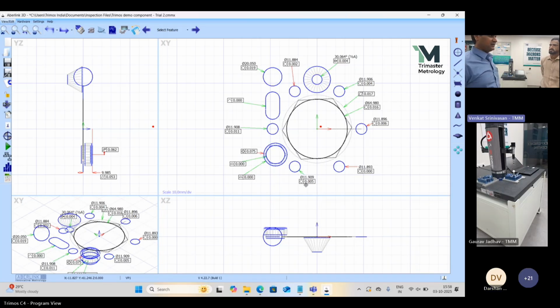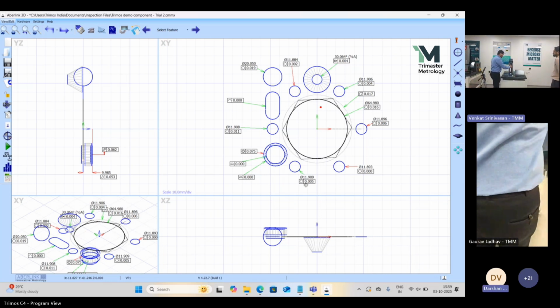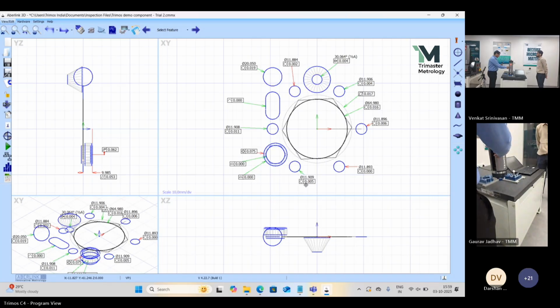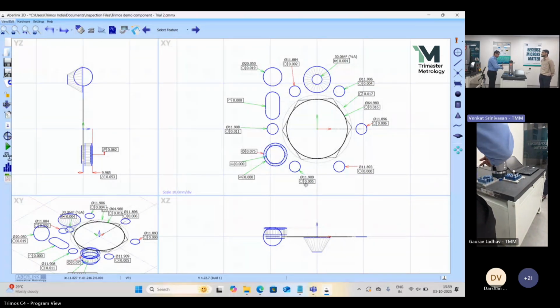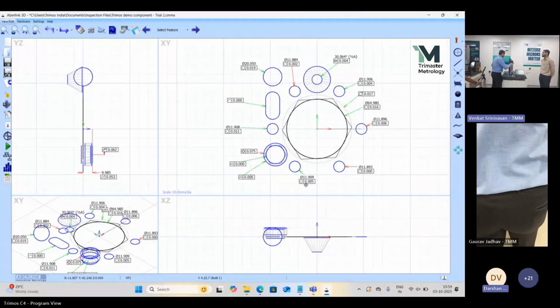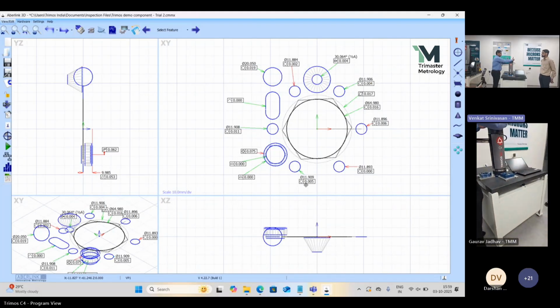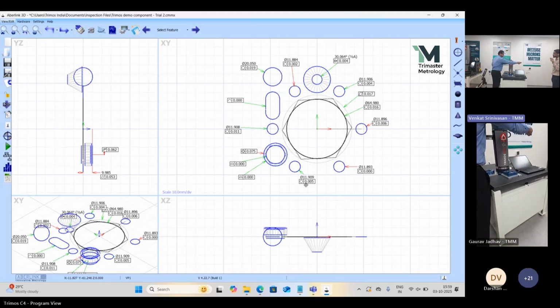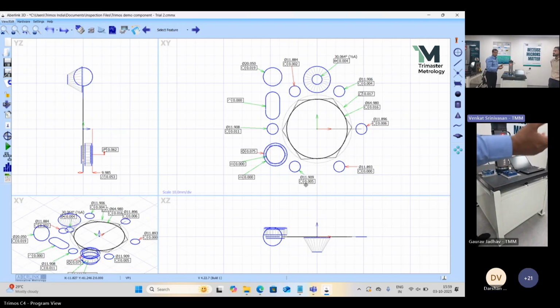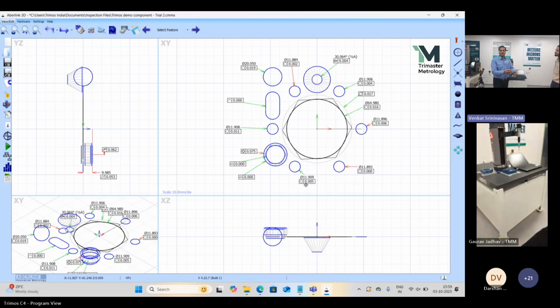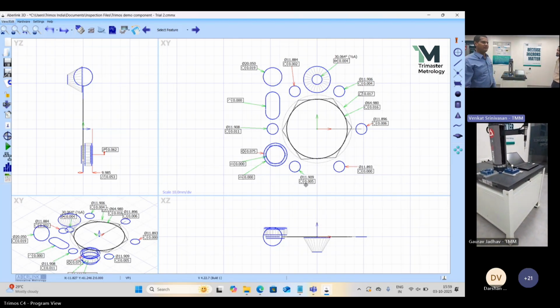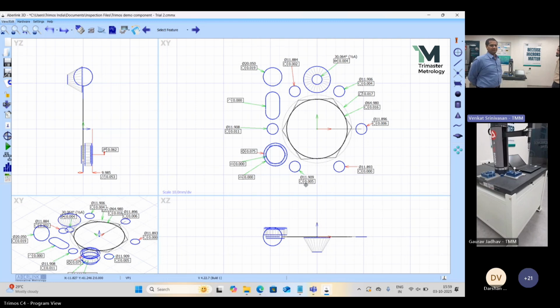If you put the part surrounding the C4, you can measure up to 700 millimeters diameter, because this here is 270, we extended, and this will move. This diameter is 160. So 270 plus 270 is 540, plus 160. The total reach will be about 700 millimeters. So you can measure, say, about 10 or 15 millimeters under that. So you can say 680 millimeters, you can measure safely.